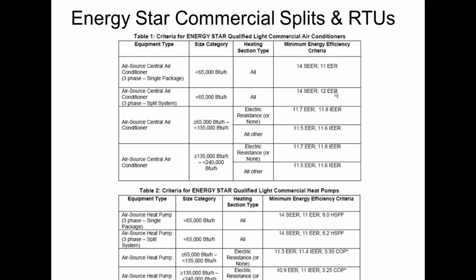When you get to the bigger categories of units, so commercial sized units, if you will, which means you're more than 5 tons, then you have to pick, just like with codes, from a table that says electric heat or no heat, or all other. So gas heat goes under all other. For a gas packaged rooftop unit, you would have to be 11.5 EER and 11.6 IEER. EER, once again, is full load efficiency on a 95-degree day. IEER, Integrated Energy Efficiency Ratio, is your part load efficiency.